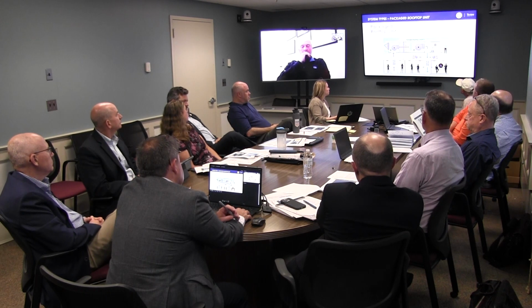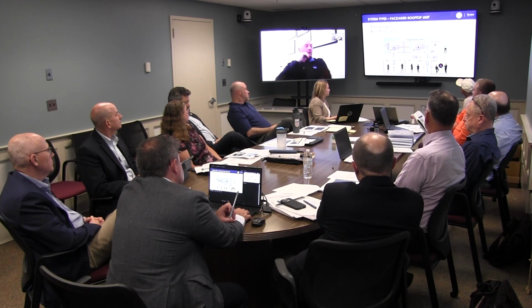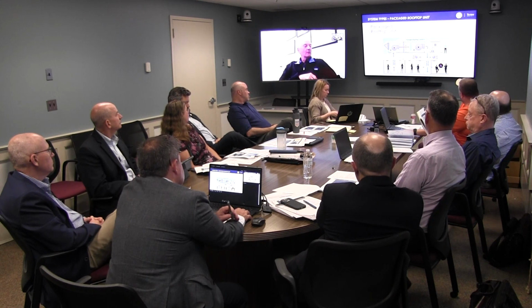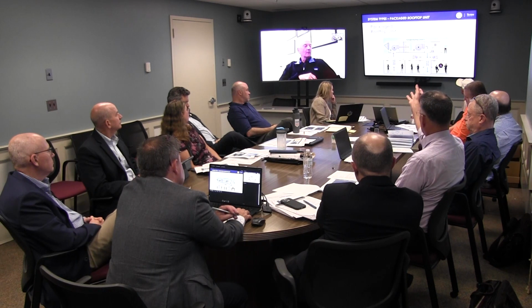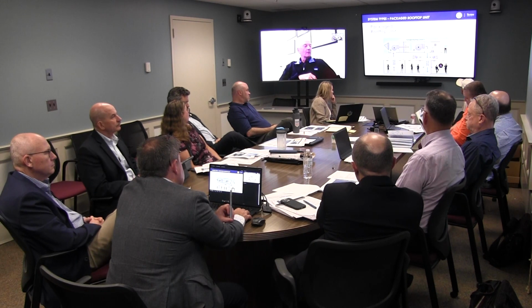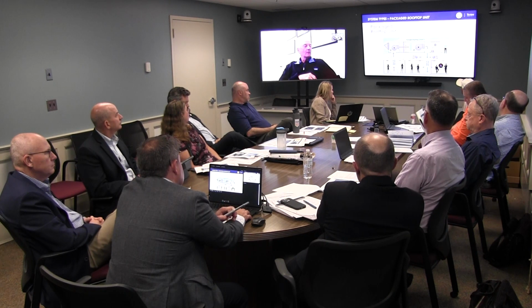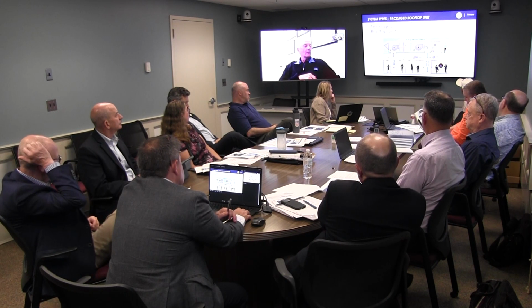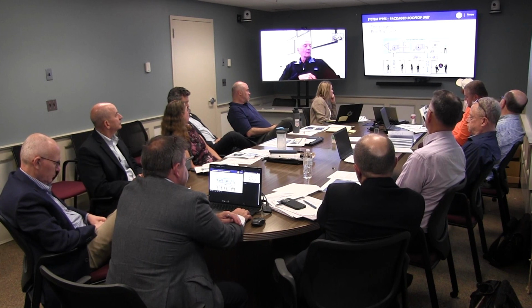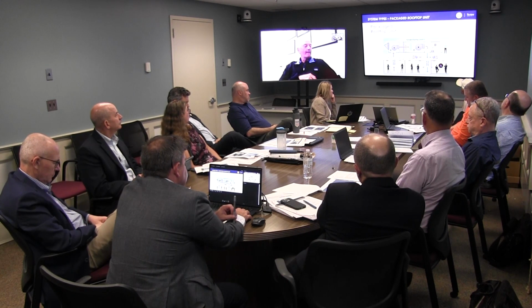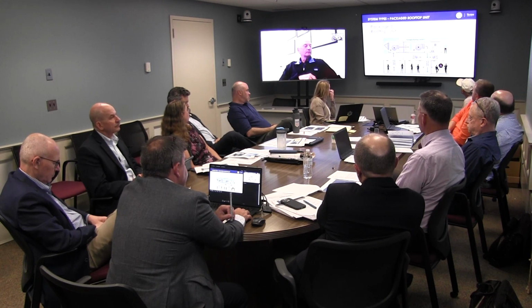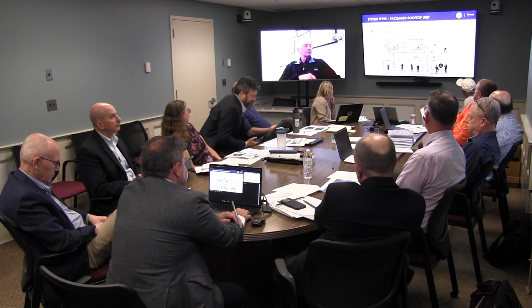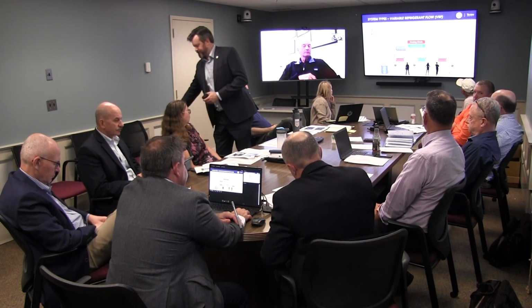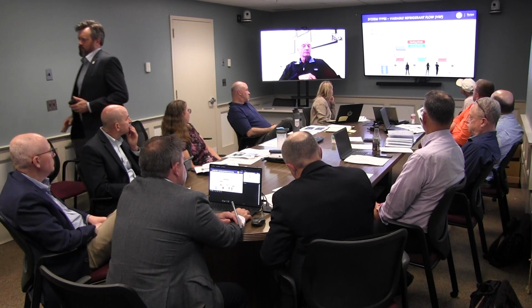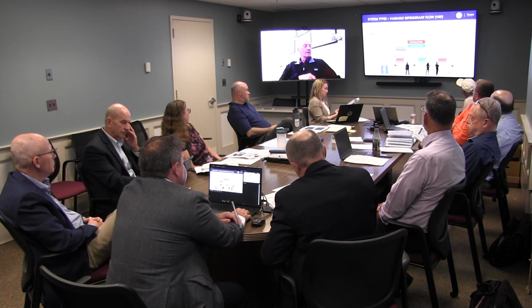Okay. Package rooftops. Again, this is your cheapest cost usually. Usually goes to a variable air volume approach. You can do packaged DOAS on a roof like this and feed chilled beams, something similar. But what VAV allows you to have is individual control on an individual space, fed off a larger, more centralized type of equipment. There's a lot of schools that still do this. It's not one of your most efficient approaches. VRF, we're pretty much going to pass on this because the facility really does not want us to explore this. Not much more to say on that.